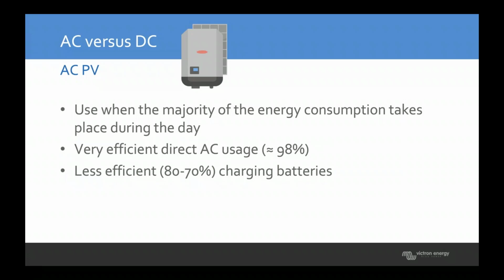AC PV inverters from Fronius are extremely efficient at converting panel power to an AC sine wave to power AC loads, right? That's what they're optimal at, and they're much more efficient at doing it than the battery inverter is converting DC power to AC power from a battery bank. So that's one reason to go. However, they're less efficient when you want to charge a battery. And you can see why. You have to go through the transformity step of DC from the panels to AC to the Fronius to DC back again through the Multi Plus to charge the battery again. So there's an extra step of transformity that has to happen in that step. So if it's predominantly nighttime or predominantly battery charging, you're better off with a direct DC to DC charge.